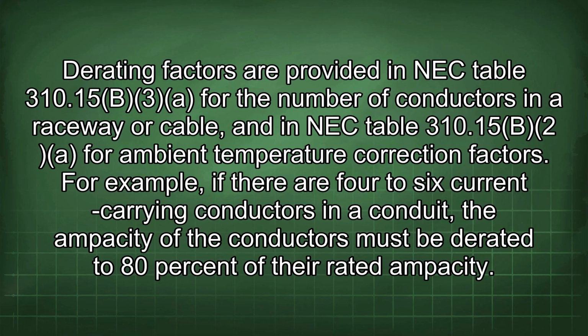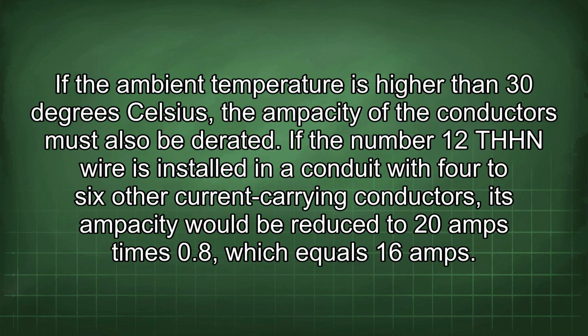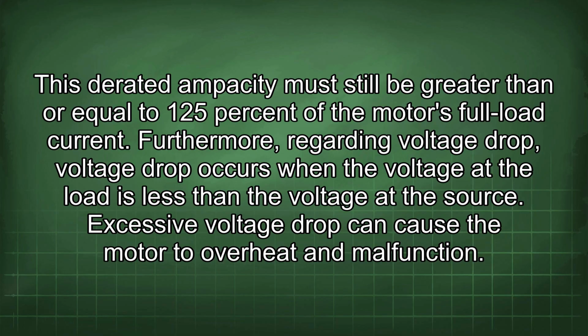For example, if there are 4 to 6 current-carrying conductors in a conduit, the ampacity of the conductors must be derated to 80% of their rated ampacity. If the ambient temperature is higher than 30 degrees Celsius, the ampacity of the conductors must also be derated. If the number 12 THHN wire is installed in a conduit with 4 to 6 other current-carrying conductors, its ampacity would be reduced to 20 amps times 0.8, which equals 16 amps. This derated ampacity must still be greater than or equal to 125% of the motor's full load current. Furthermore, regarding voltage drop: it occurs when the voltage at the load is less than the voltage at the source.